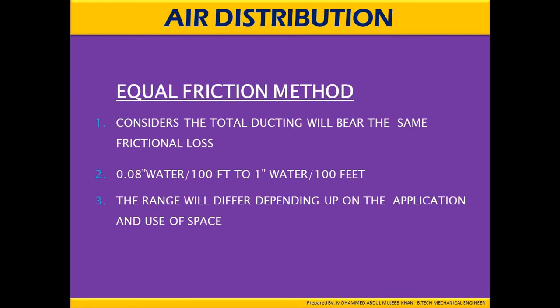The equal friction method considers that the total ducting will bear the same friction losses throughout — for example, 0.08 inches of water per 100 feet. This is a typical example where we need to consider that ducting will bear the same friction loss throughout its sizes. The range will differ depending upon the application and the usage of the space.